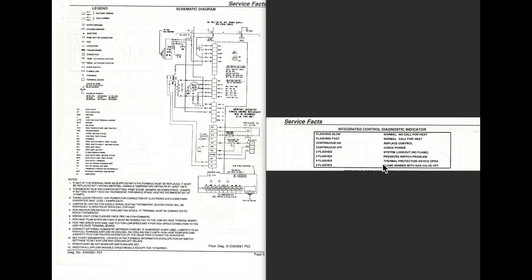Four flashes, thermal protection open. What we've got there is we've got two limit switches on this thing, and those limit switches have to work. They have to be closed, or this thing's not going to go any farther.